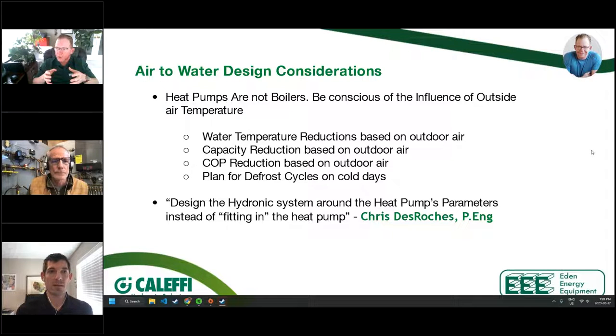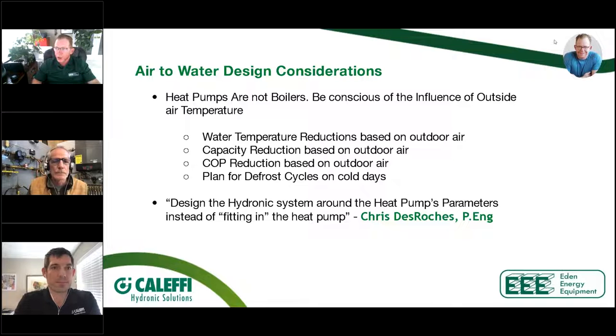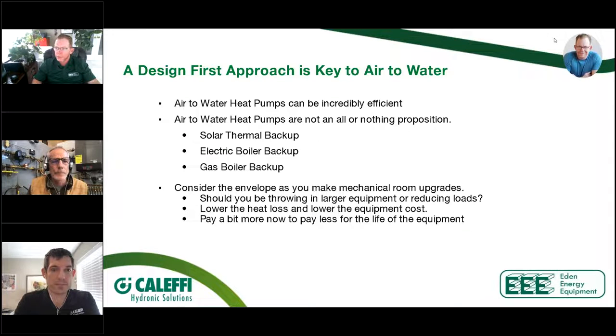And the difference with a heat pump is that it's not just a matter of impacting efficiency. You are dramatically impacting the life of that equipment. You can kill a piece of equipment in 6 months by not piping it properly or designing it properly, whereas the boiler that Bob is talking about might last 7 or 8 years and nobody will know better. So we definitely need to try to plan and accommodate around what a heat pump can and cannot do.